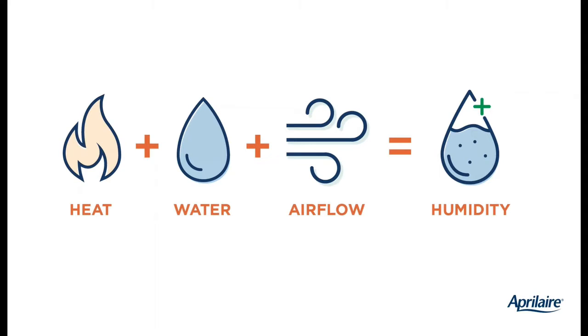If you've got an application and you're wondering, can I install it like this or like this, keep those three things in mind. Where am I going to get the heat from? Obviously water. And then am I going to have sufficient airflow for this application? That'll help you decide if an install is a good choice. It'll also help you when it comes to if you call in with any troubleshooting questions. The questions are basically going to revolve around making sure we've got the right amount of heat, the right amount of water, and the right amount of airflow. If we do, we should be getting proper humidification being produced by the humidifier.